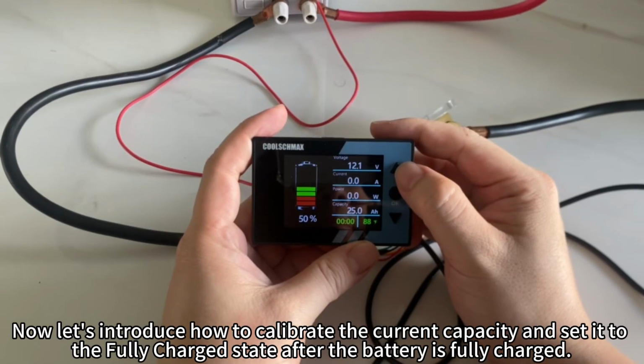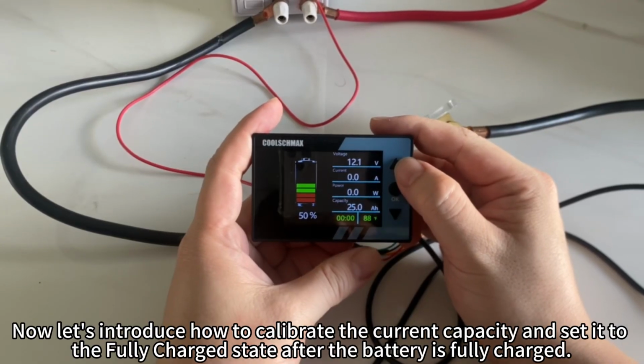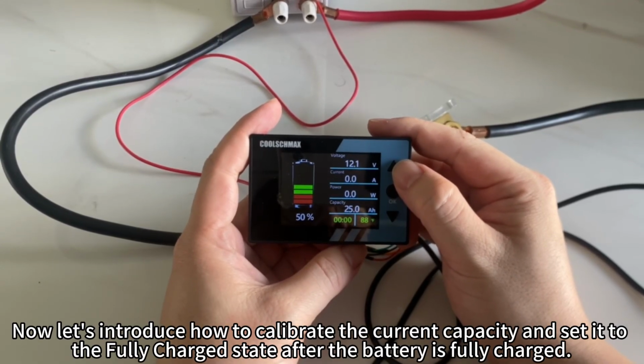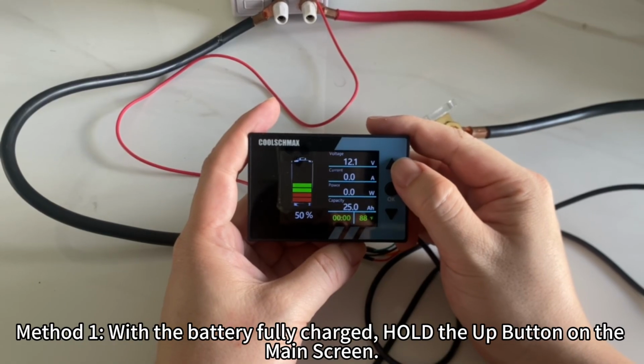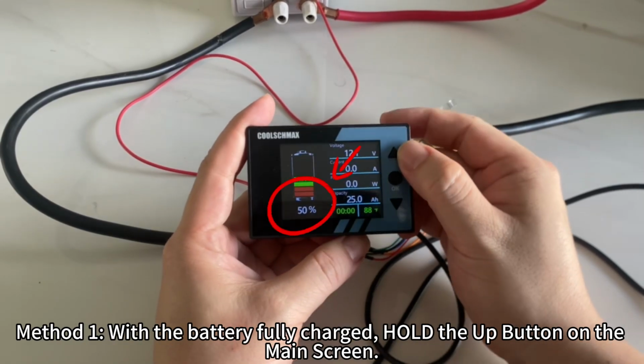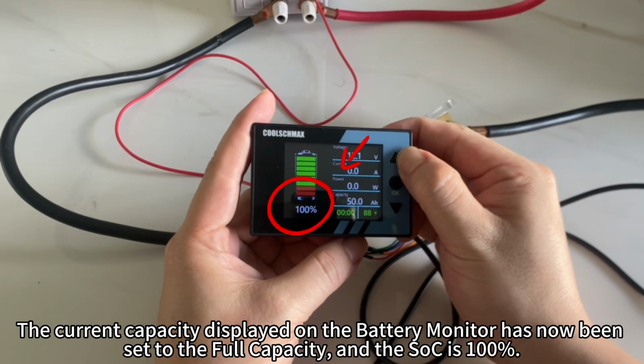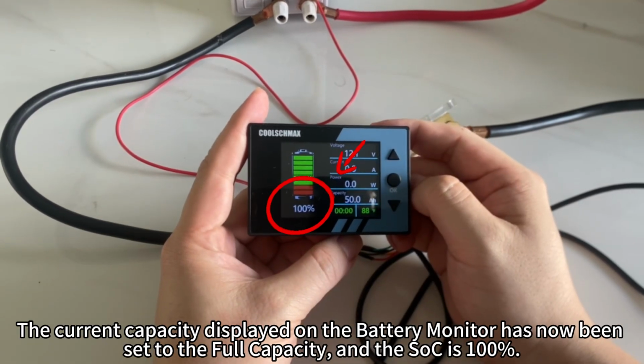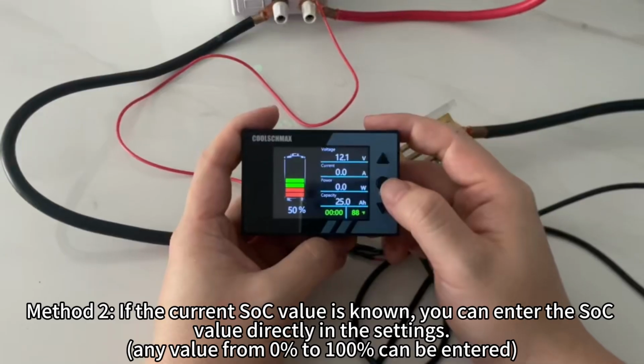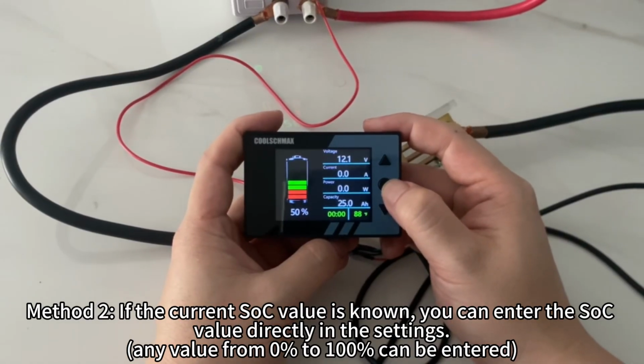Now let's introduce how to calibrate the current capacity and set it to the fully charged state after the battery is fully charged. Method 1. With the battery fully charged, hold the up button on the main screen. The current capacity displayed on the battery monitor has now been set to the full capacity, and the SoC is 100%. Method 2. If the current SoC value is known, you can enter the SoC value directly in the settings.